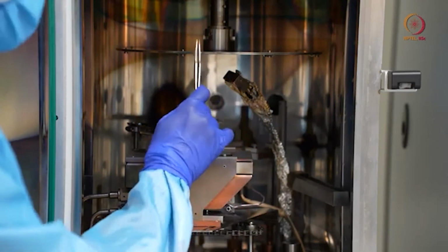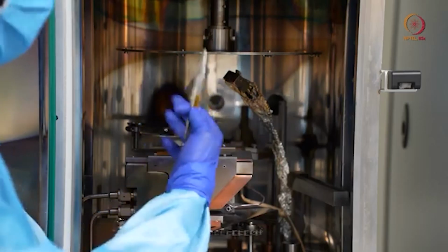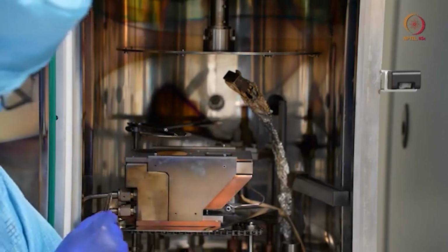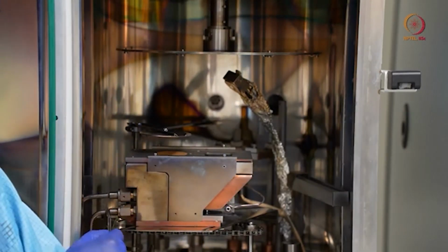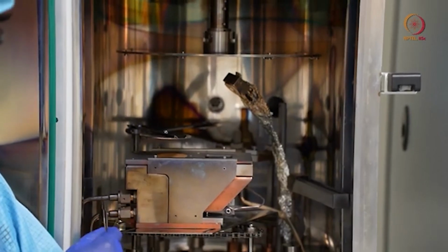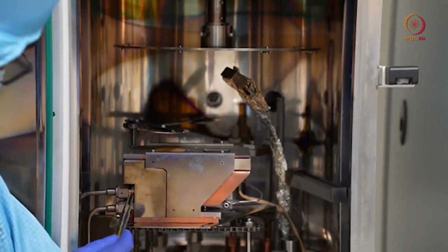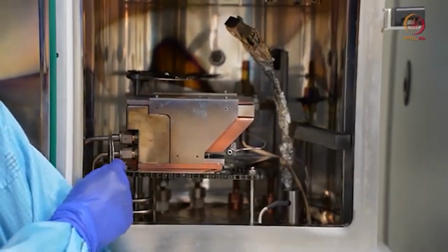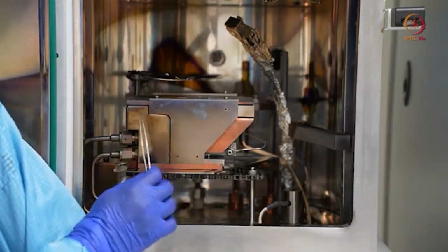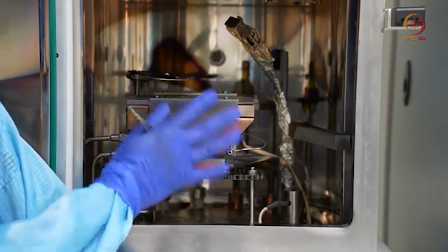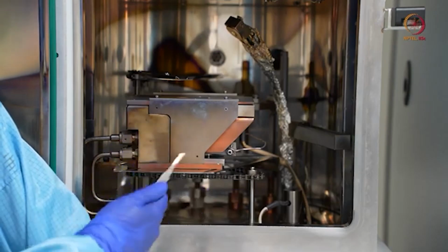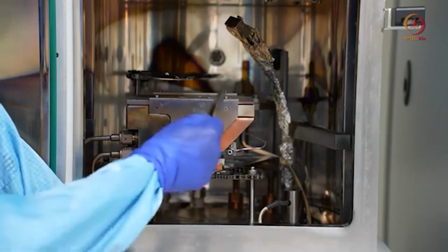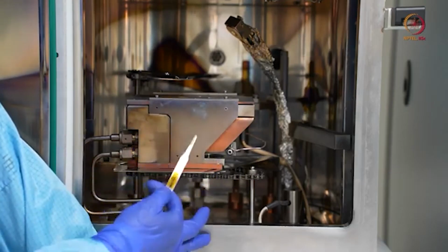So here is the chuck. We will show the chuck again when we load the sample. And here you can see two pipes. Basically these pipes are from the chiller unit and to the chiller unit. One is inlet, the other one is outlet. This will be useful to cool down the filament and this whole module during deposition, and even after deposition you can keep your chiller on so that water will flow through this and it will be cooled down.